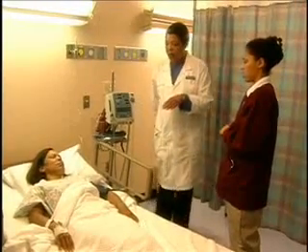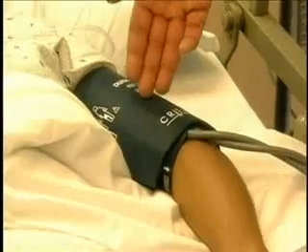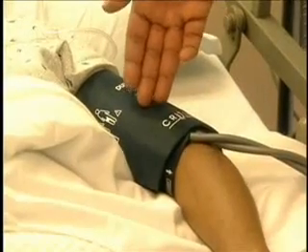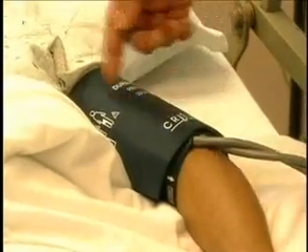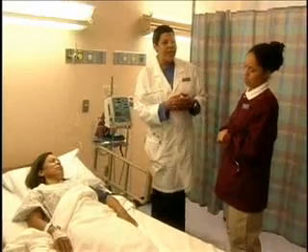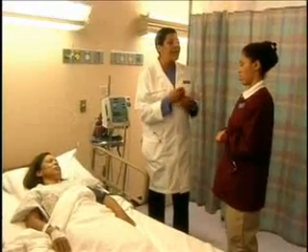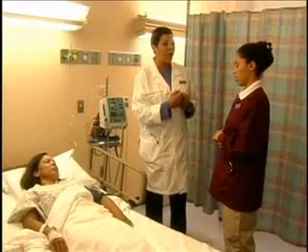The cuff is applied in the same way with the microphone or the pressure sensor positioned directly over the artery. Okay. And how it works, it determines blood pressure by analyzing the sounds of the blood flow through the artery or by measuring oscillations. That's pretty cool.